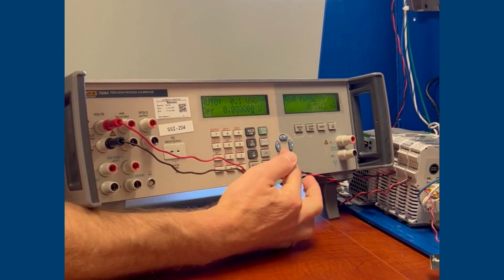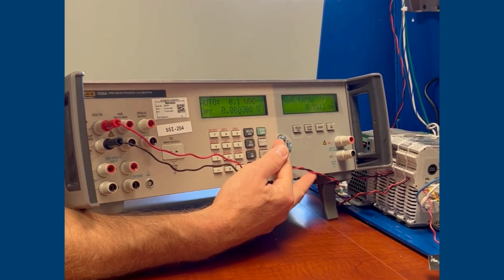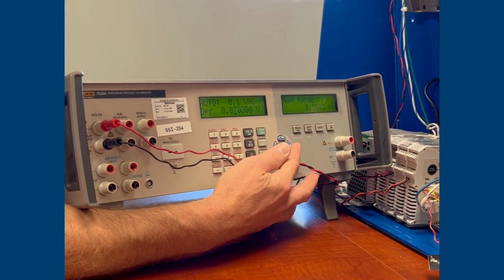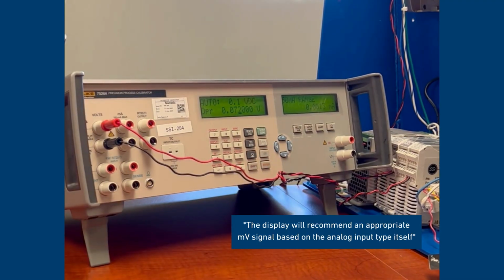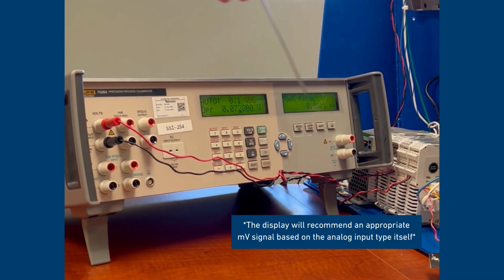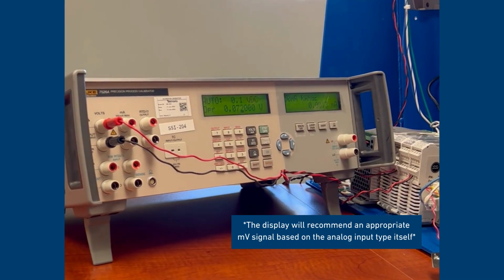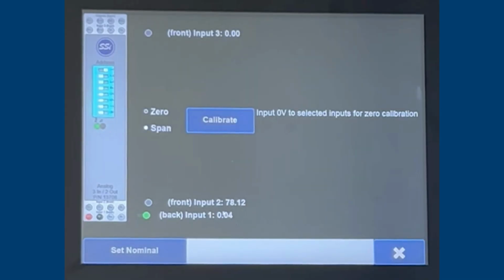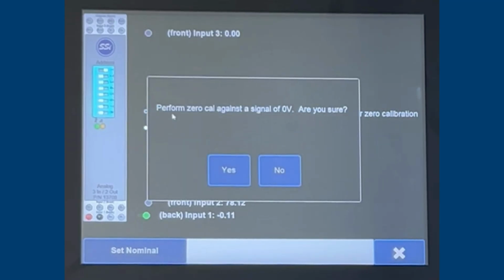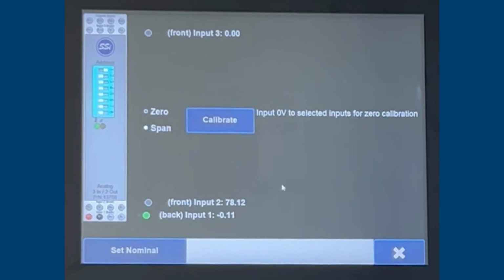Then when we need to do a span calibration, we would come in and adjust to 72 millivolts. This is sourcing through copper wire 72 millivolts for the span input of input 1 calibration. Once we see that the input is reading what we're sourcing in for 0 volts for a 0 calibration through copper wire, select the Calibrate button. It confirms we are performing a 0 calibration against a signal of 0 volts. We are sure, and then we wait for the progress meter to advance as the calibration processes.